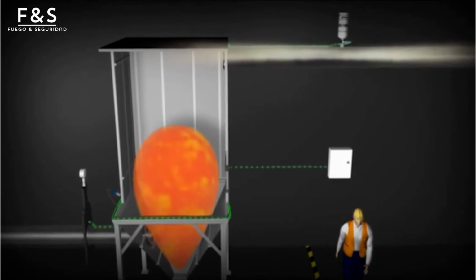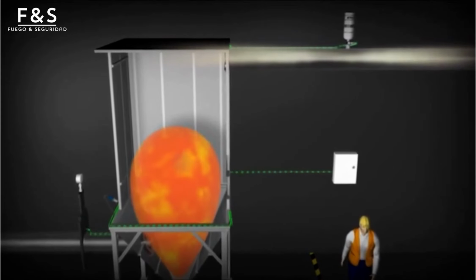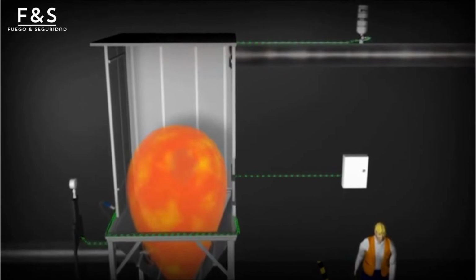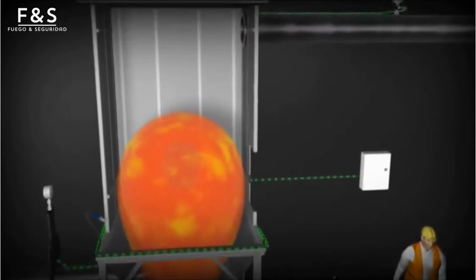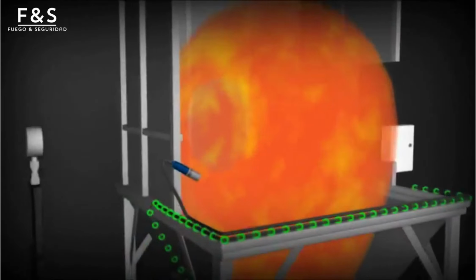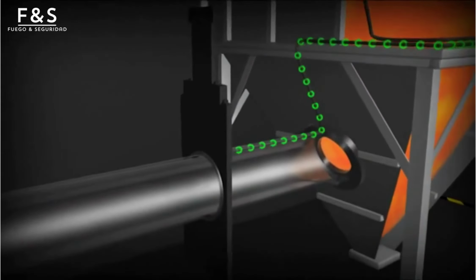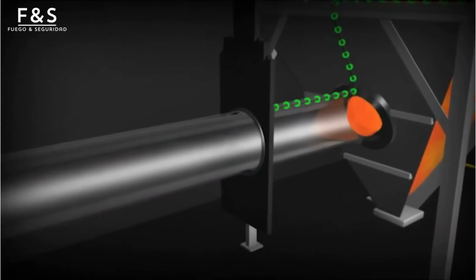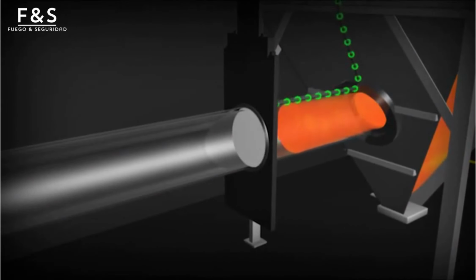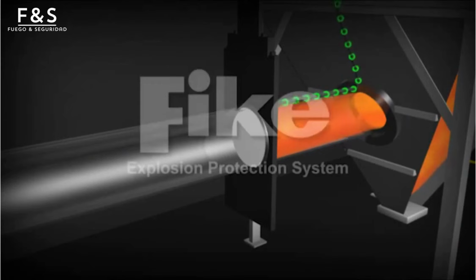The system maintains a history of the event for future reference. Simultaneously, the gas cartridge actuator drives the piston on the isolation valve, closing the slide gate and providing mechanical isolation, which prevents the propagation of the explosion through the ductwork to interconnected vessels.